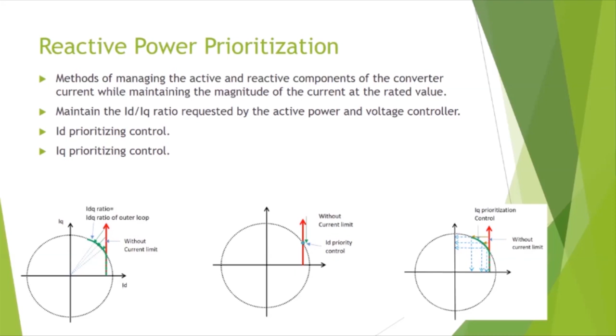In the middle, if the desired current is outside the circle, you simply bring it down, meaning you maintain the desired direct current, or the in-phase current, at the expense of quadrature current. The one on the right is the opposite. You maintain the desired quadrature current at the expense of in-phase current. And for recovery of the converter from a large fault, we found that the Iq prioritization, the third one on the right, works best.